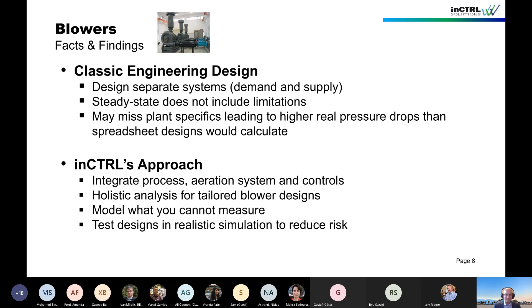One thing that has been done in the past is that fairly cheap butterfly valves are used, because they are a lot cheaper than some of the newer valves that are out there. But they provide somewhat limited controllability of the airflow, and the positioning accuracy isn't as good. So there are newer valves now that are much more precise and have much lower pressure drop, but they can be more expensive. So you have to make a decision on whether the added expense is worth the improvement in control performance.